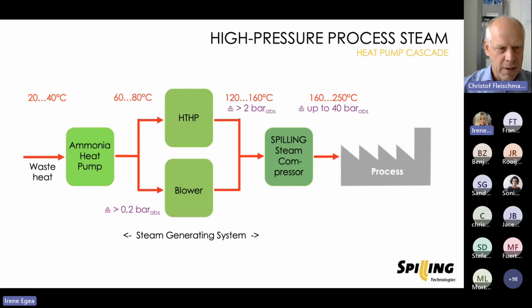Another example is where the cooling water as heat source at a chemical plant in France shall be used. It has about 27 to 35 degrees Celsius, and again 10 bar steam shall finally be produced from that, also in this 3-stage combination. And another project, what I think is now close of realization, is installation in Austria, where the exhaust heat from chillers shall be compressed upwards to finally also 12 bar steam pressure level in a pharmaceutical plant.